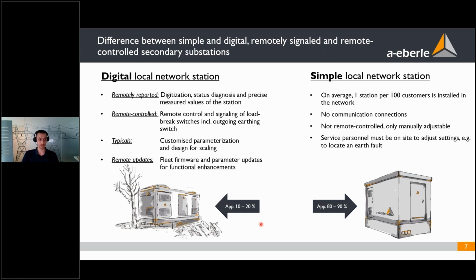The typicals for these stations are also customized parameterization and design for scaling, especially with a focus on personnel costs. You would need hundreds of these stations with many devices inside of each station. So yeah, they should be beforehand designed for scaling. And one of these scaling points is remote updates. So it should be possible to perform fleet firmware and parameter updates for functional enhancements, again with the focus on personnel costs to be reduced.